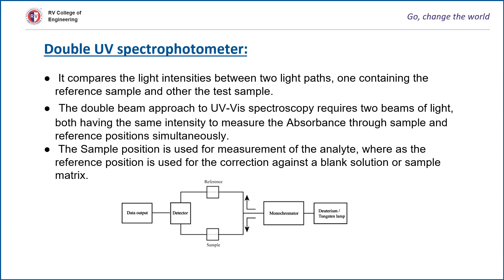The double beam UV spectrophotometer compares the light intensities between two light paths, one containing the reference sample and the other the test sample. The double beam approach requires two beams of light, both having the same intensities, to measure the absorbance through sample and reference positions simultaneously. The sample position is used for measurement of the analyte, whereas the reference position is used for correction against a blank solution or sample matrix.